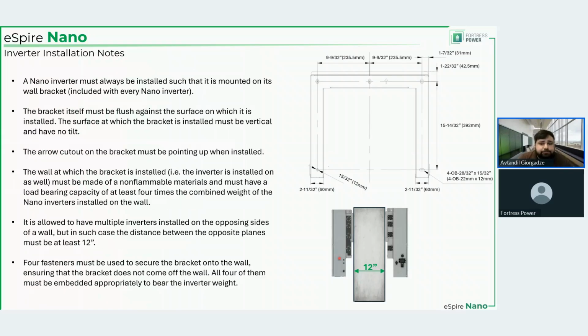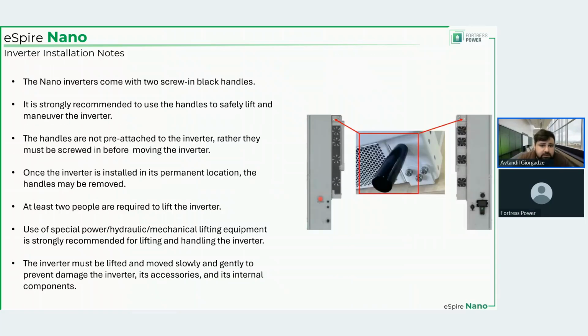Moving on. So this we went through. I also mentioned the handles that are included with the inverter. There are 2 of them. They are screw-in handles. Once you open the box, the handles are included, but they're not attached to the inverter, so you screw them in. You don't have to use a tool; hand tight is good enough. You put in a handle on each side of the inverter, and that allows you to lift it more easily because the inverter itself doesn't have any other handles whatsoever. When you install the inverter, you are allowed to remove those handles. But if you prefer to keep them on, that's also fine.